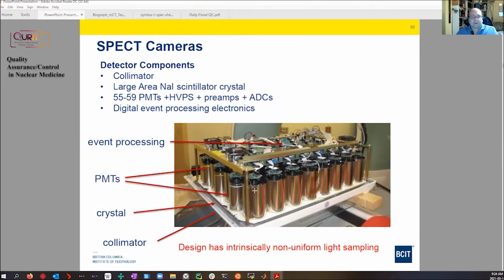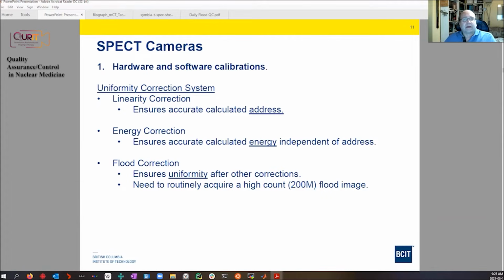Now, one of the problems with this design is that it does not give uniform sampling of the light from the scintillator. PMTs, you see, are circular, and there are gaps between the PMTs. So if the scintillator light goes between the gaps in the PMTs, we don't detect it. That can cause some systematic errors in the addressing, and these are some of the things that need to be addressed in a gamma camera. Underneath here is the collimator, here's the crystal, here are the PMTs.